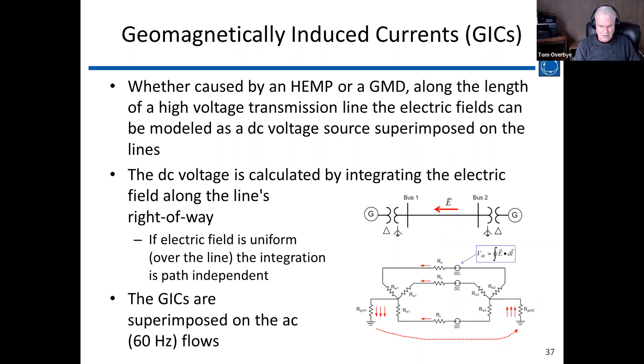As we solve this DC circuit, we have to augment it with some additional fields not found in a typical AC analysis. These include how your electric grid is grounded through the transformers. The delta windings don't have a ground path, but the Y windings do. We also have to know the substation grounding resistance. Luckily, from an HEMP analysis perspective, these are values utilities now have because of the work they've done in GMD analysis. So while these are newer fields to deal with, they're ones electric utilities already have.